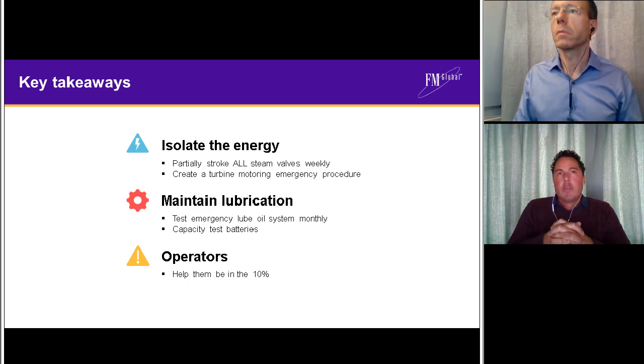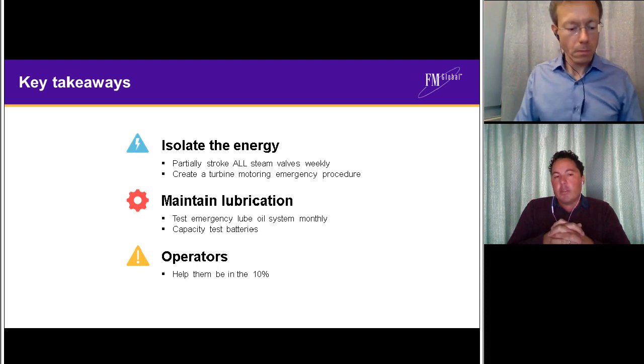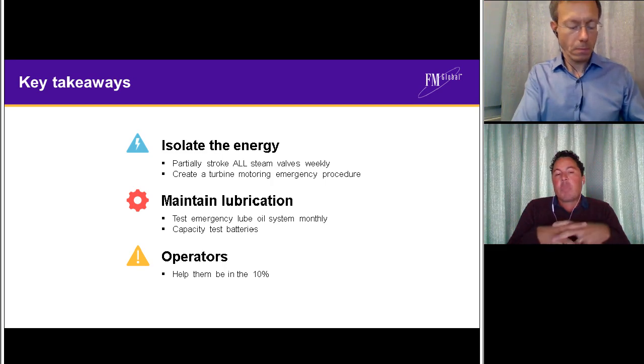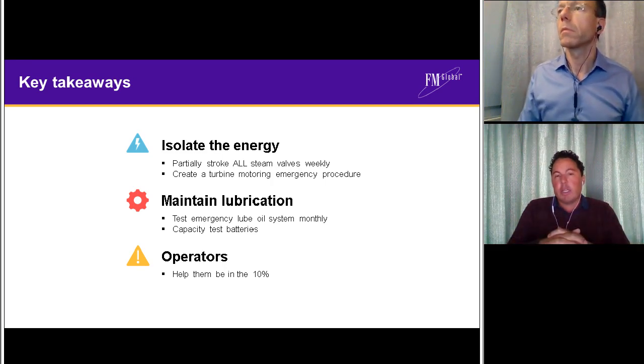One of the elements that crops up often in our environment is what non-destructive examination should be done to eliminate the possibility of cracking on stress risers. Traditionally you're seeing this in the roots and slots of the steam turbine blading. We often have these conversations with clients and OEMs around the best way of proving that that's not a concern. I think we know it's a susceptibility of all steam turbines, and ultimately our goal is to help our clients be absolutely confident that they are not going to fall foul of a crack that propagates and lands up in a blade liberation event.